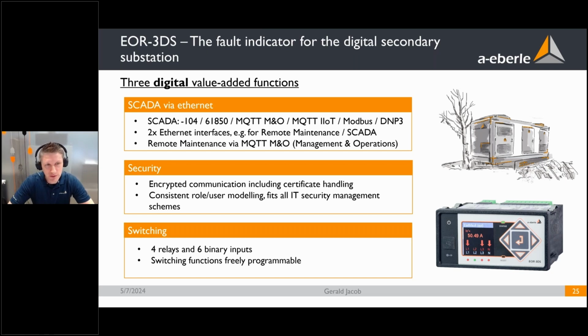Second big topic is security. So we have encrypted communication, including certificate handling. As soon as you have Ethernet protocols, you have to take care of IT security. And therefore, we also have a user role model regarding the panel and also the TCP/IP communication with our software. And third big topic, switching. The device is meant for digital secondary substations where you also want to have remote indication and remote control. And for this remote control, we have in total 4 monostable relays in the device, and 6 binary inputs and PLC functionality. That means the switching function, for example, can be customer specific if required.